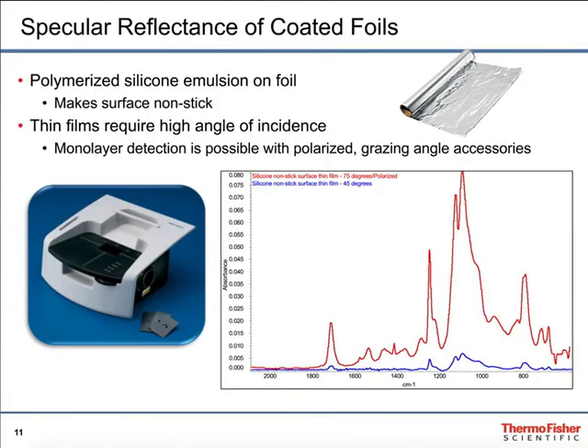Here's an application showing why you would use different angles. This is aluminum foil with a thin coating on the surface. If you look at the two spectra shown, the blue one involved bringing the beam in at near 45 degrees, whereas the red one involved bringing the beam in at about 75 degrees. You can see the big difference in the signals — the 75 degrees makes for a much more intense signal. This is a very thin film, which is why this works this way. With a thick film, you'd prefer to use the steeper angle, because otherwise your signal would be totally absorbing.